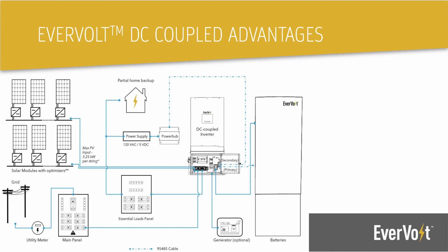This is a look at a DC coupled Evervolt system. So you'll see it's very similar to the AC coupled, with the main distinction being that the PV array is going to be tied directly into your Evervolt inverter in PV array input. Everything else is essentially the same on the system. Main advantages of DC coupled is the simplicity in that you only have a single inverter that is acting as the brains for the entire system, including the PV array.